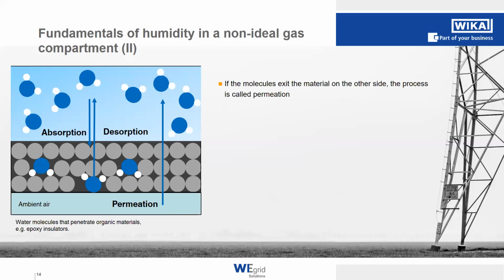Also, we have the process of permeation, where water molecules try to get from the outside into our gas compartment. And why is that? Because we have quite a high humidity outside of the gas compartment in our atmosphere, and then we have a very dry gas compartment. The gas is very dry. So by nature, the water molecules try to get into that very dry area. This process goes in both directions. Also, from high to lower pressure is the preferred direction of the molecules. But like I said just before, since we have a very dry gas, the humidity always tries to counterbalance itself into the gas compartment.